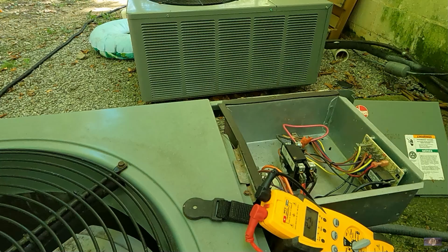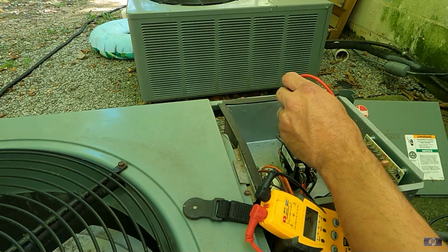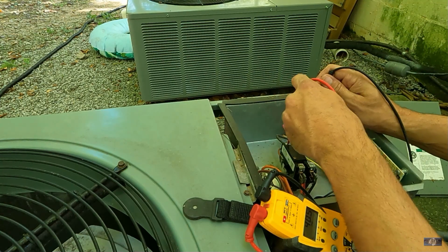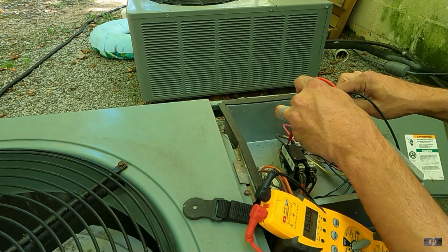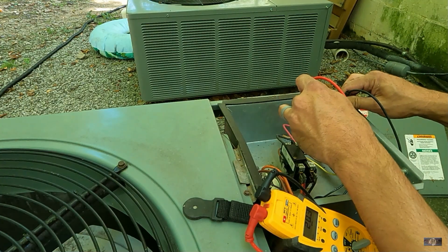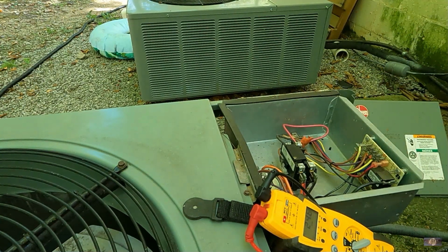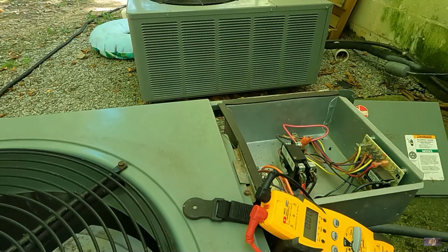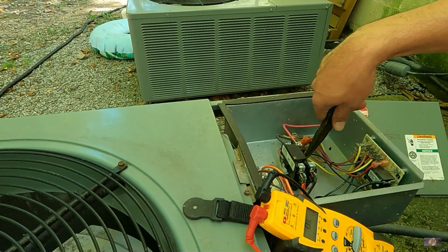Alright, I shut the unit down at the thermostat, put it to off position, killed the breaker inside, or the disconnect. Just gonna test voltage, make sure I don't have anything here before I get zapped. Alright, I'm good. Let's go ahead and test this contactor coil here.